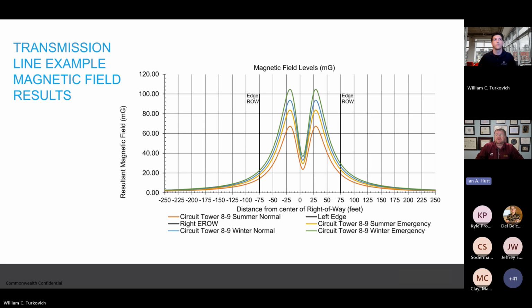Depending on state and state requirements, we may have to look at those conductor ratings when determining magnetic field levels. Sometimes we can use actual loadings. So it just depends on the scenario and the situation what value we use. Because generally the rating itself is going to be much more severe than an actual loading, it tends to give us more severe results. And this is a nice example of exactly that here. As we look at these different graphs and colors, we can see everything from a summer normal rating to a winter normal rating, all the way up to the summer emergency and the winter emergency ratings.